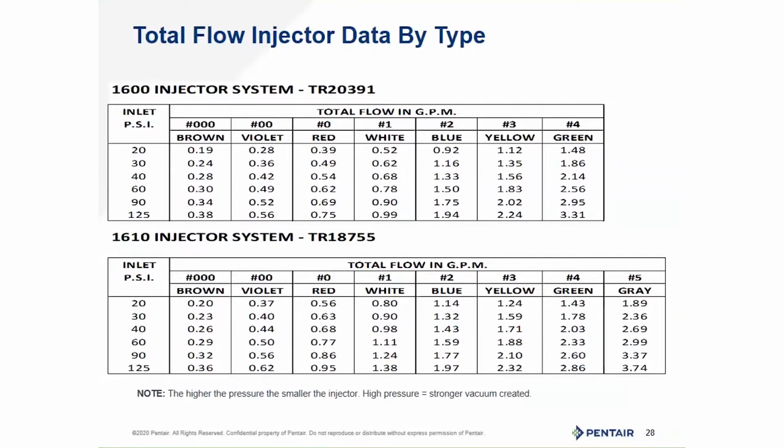As we're shooting that thin stream of water down that throat, we're pulling the air in that throat with us, and that creates a pressure drop, and that will draw air in, because anytime you have a pressure drop, you're creating kind of a vacuum, and nature wants to fill that vacuum. In this case, it's brine from the brine tank.